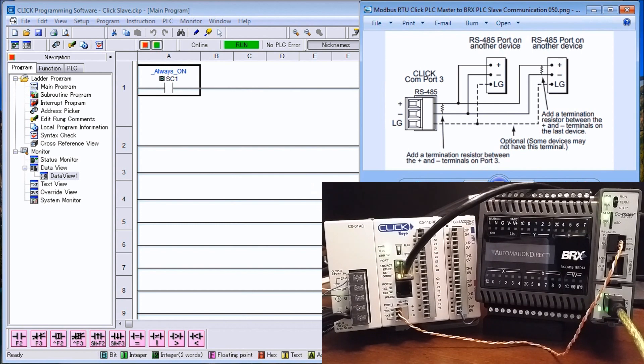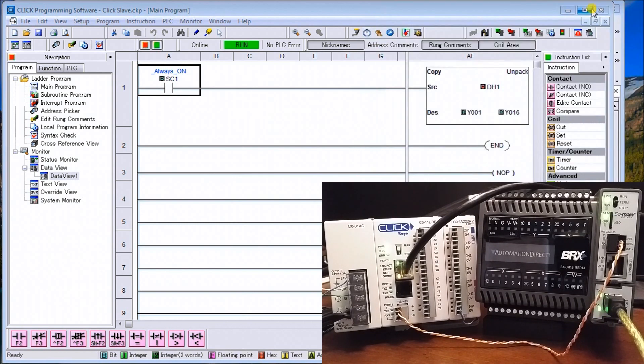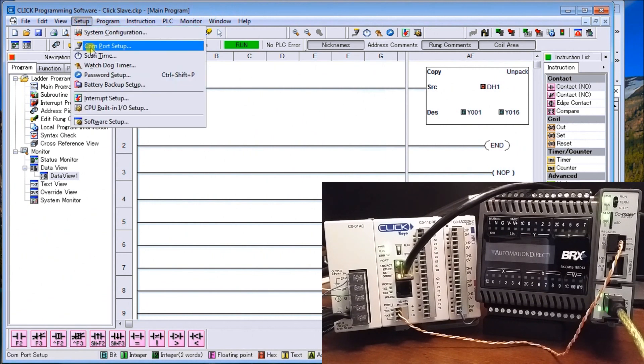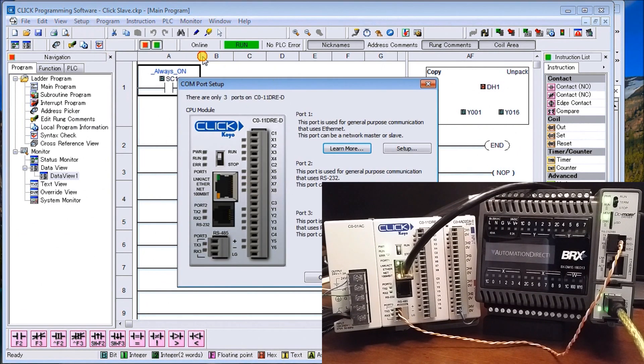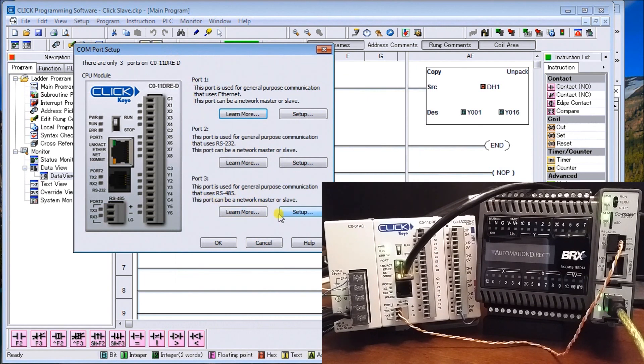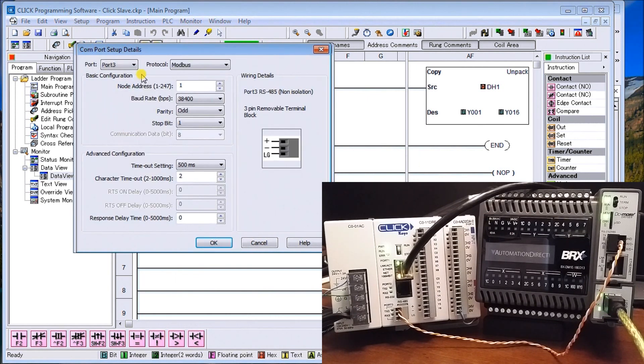Looking at the Click PLC first — we're online and communicating. Under Setup and Port Setup, going down to COM port number three, you can see that the protocol is already set to Modbus. Our node address is number one, baud rate is 38.4k, odd parity, one stop bit, and eight data bits. There's also the wiring diagram shown for that port.